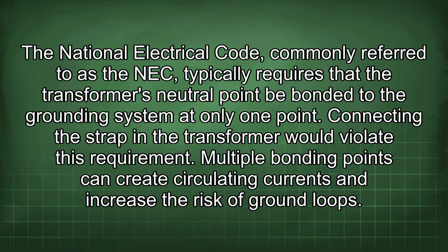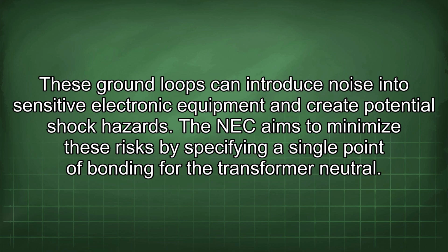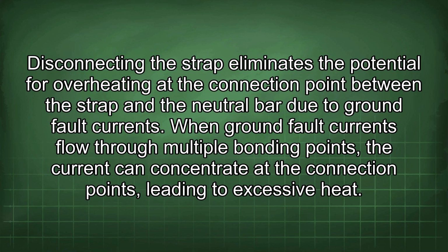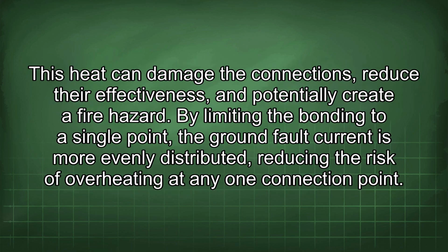Multiple bonding points can create circulating currents and increase the risk of ground loops. These ground loops can introduce noise into sensitive electronic equipment and create potential shock hazards. The NEC aims to minimize these risks by specifying a single point of bonding for the transformer neutral. Disconnecting the strap eliminates the potential for overheating at the connection point between the strap and the neutral bar due to ground fault currents. When ground fault currents flow through multiple bonding points, the current can concentrate at the connection points, leading to excessive heat. This heat can damage the connections, reduce their effectiveness, and potentially create a fire hazard. By limiting the bonding to a single point, the ground fault current is more evenly distributed, reducing the risk of overheating at any one connection point.